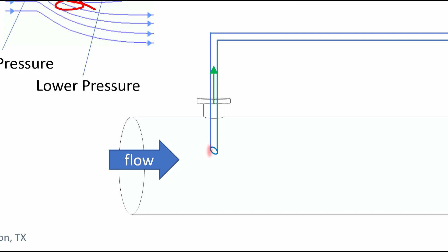Commonly, in systems like this, if the direction of flow is coming in, they cut a probe angled towards the direction of flow. The flow impacts on that, drives its way up through that piece of tubing, and runs across. They have another probe cut at the opposite angle, away from the direction of flow, which creates a low pressure zone, so you get continuous flow through that loop and vaporize that flow. This gives you a faster response at the vaporizer.